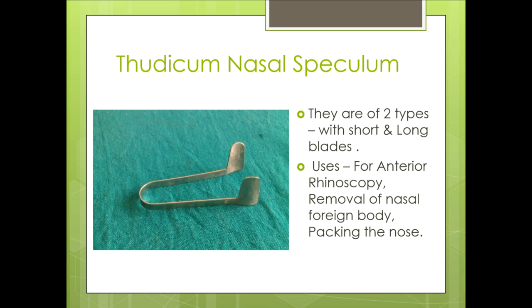This is the Thudicum nasal speculum. Usually we will use it in the OPD, outpatient department, to examine the anterior nasal cavity. Here we will hold it with the thumb and index finger. These are the prongs. We will close them during the insertion into the nasal cavity. Then we will open so that we can widen the anterior nasal cavity.